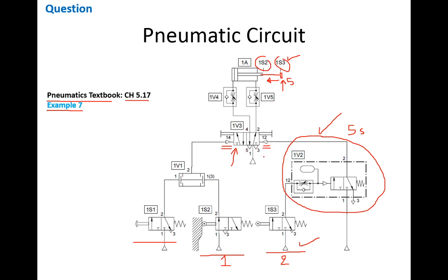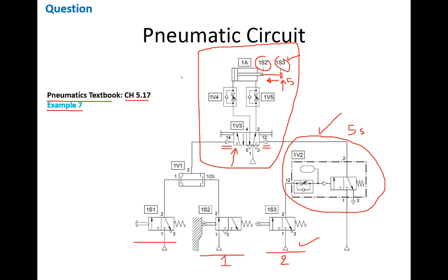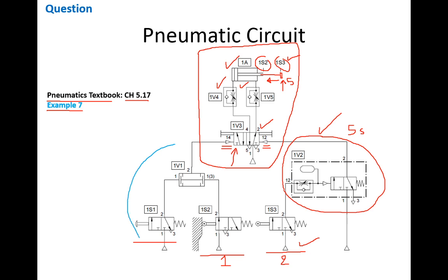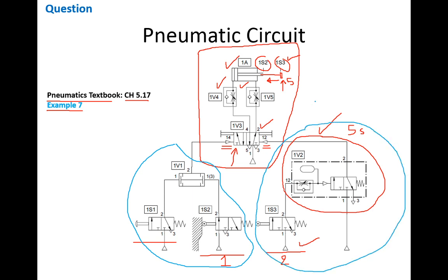When we convert this to an electrical or electro-pneumatic system, the double pilot DCV will be replaced by a double solenoid. Every time we think about converting a pneumatic circuit, we should keep in mind what is preserved after the conversion. The pneumatic part — the DCV, the one-way flow control, and the cylinder — will not be altered. The part that is going to be changed is basically the control part and the input signal part, which will be replaced by the electrical circuit.